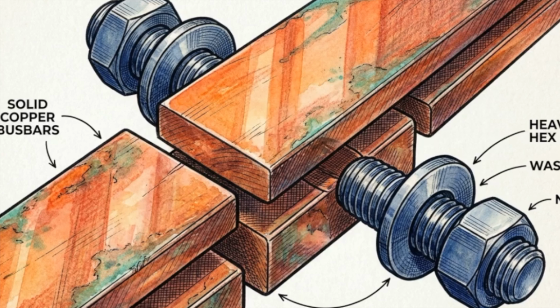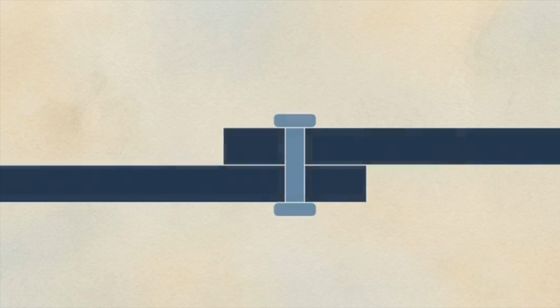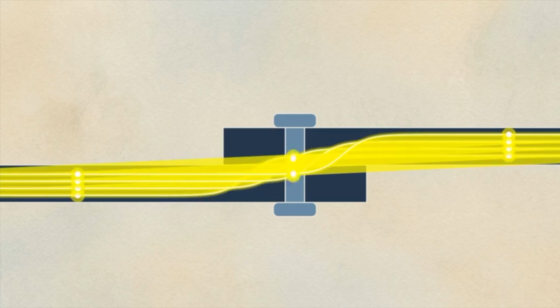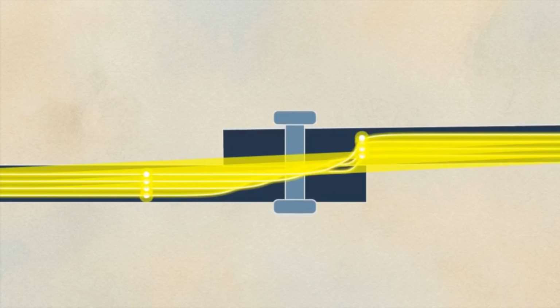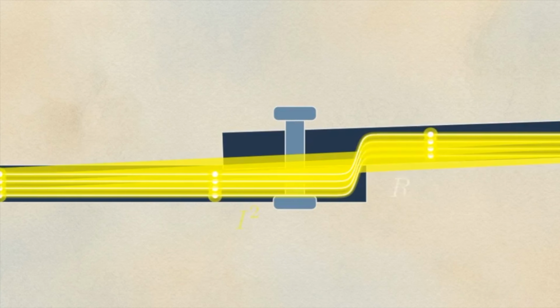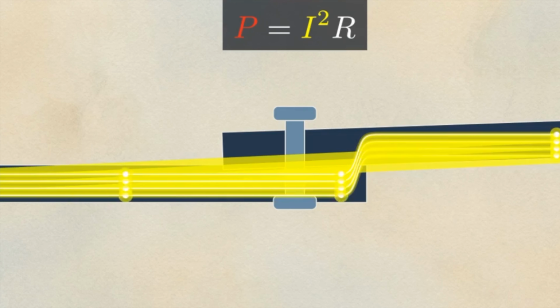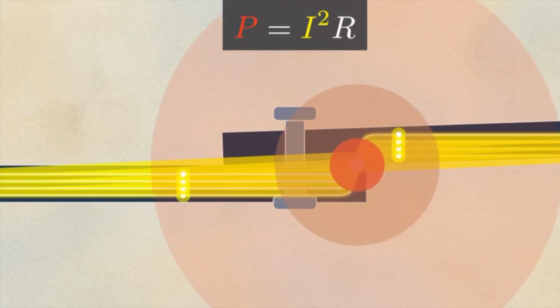In industrial switchgear, constant mechanical vibrations slowly loosen the heavy hex bolts that secure electrical connections. This triggers the principle of Joule heating. As the bolt loosens, a sub-millimeter gap forms, forcing the electrical current to compress through a tiny point of contact. This creates electrical resistance, and that resistance strictly forces heat output upward.